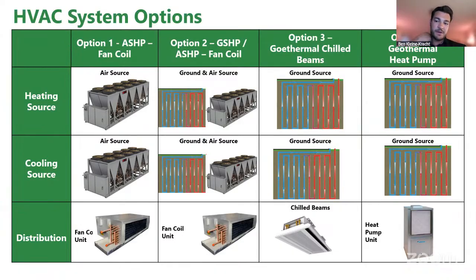No, that absolutely makes sense. The bigger spaces can definitely be a challenge from time to time. For option 4, they make 15-ton water source heat pumps. They actually have a unit that looks exactly like the one you're looking at, except it's 4 times as wide, a big unit, doing the exact same duty. We could put 2 or 3 of those in an auditorium or gymnasium. I've typically put a 15-ton heat pump like that in a gymnasium or auditorium before, and they get the job done quite well.